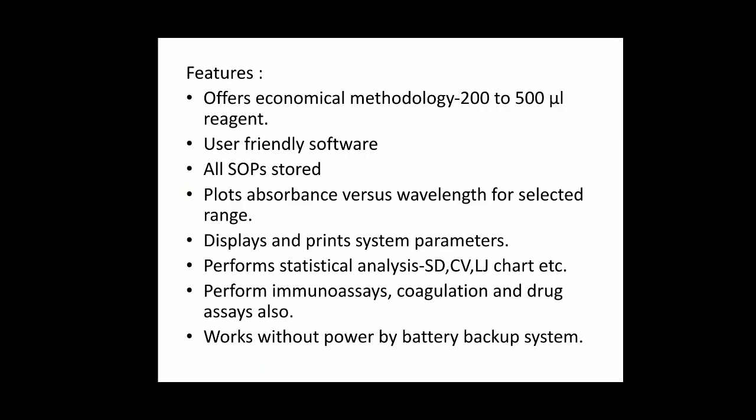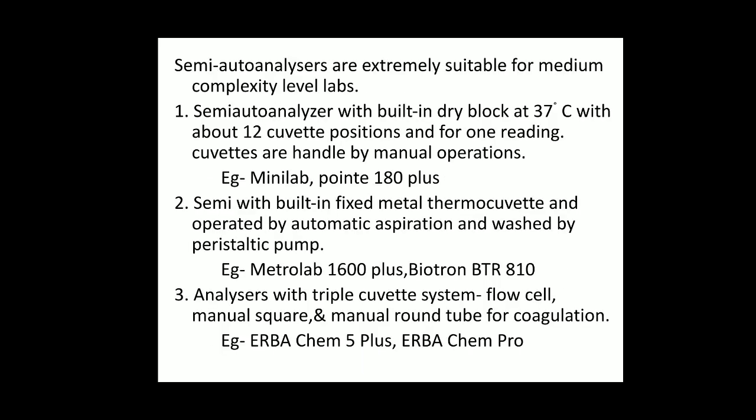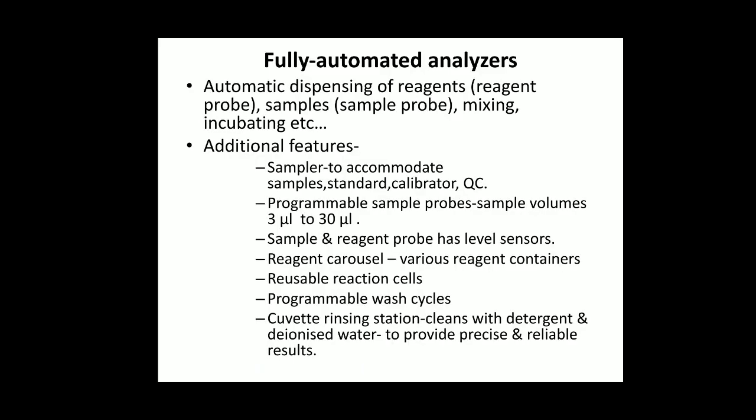The semi auto analyzer operates with a battery backup system also. Types of semi auto analyzers: one type has an incubator at 37 degrees Celsius with 12 cuvette positions — examples are Mini Lab and Pointe 180 Plus. Another type has a metal thermo-cuvette with automatic aspiration — examples include Metro Lab 1600 Plus and Biotron BTR 810. With a triple-cuvette system — which has a flow cell, manual square, and round tube for coagulation — examples are Erba Chem Plus, Erba Chem Pro.